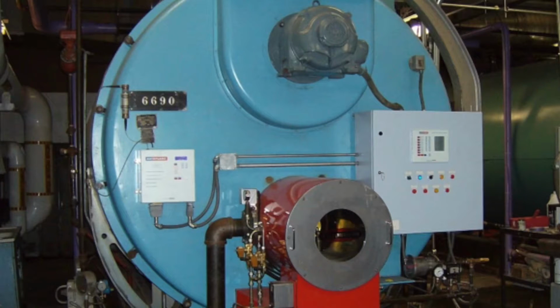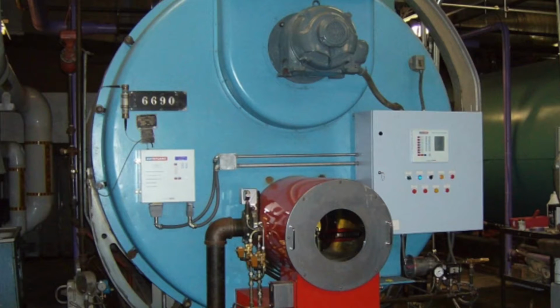We now have, instead of this screen here, a full 10.5-inch touchscreen display. It displays your efficiency levels, your fuel usage, and your carbon footprint. It tells you what your CO2 emissions are in terms of kilograms and tons, and you can now input your fuel data and fuel costs, and it'll tell you how much fuel you're using. It's a full CEMS package, continuous emissions monitoring software. There's more information here, but the other thing, as I've mentioned earlier, is if we make that talk back to the main control module here, we have what everyone calls oxygen trim. We have a 5-parameter trim where we measure oxygen, carbon dioxide, carbon monoxide, ambient temperature and pressure. So we use a 5-parameter trim.